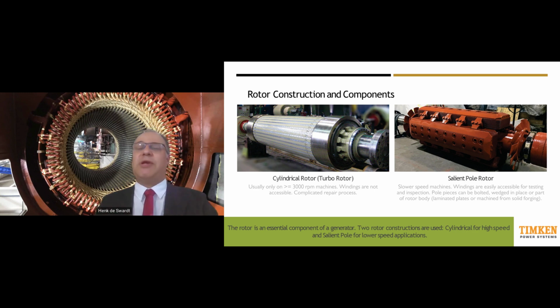And that's important because when you try and clean this machine, you basically can't. Even if the rotor is outside of the stator, it's very difficult to clean this rotor. Because often when you try and use air or dry ice, you may actually just blow contamination into the winding. So if you need to clean this winding, it is a very big deal. We always recommend that the rotor should be taken to a workshop to be cleaned there. Because if you take off the rings on the ends, the winding relaxes and you won't get it back in. In any case, more of that later.